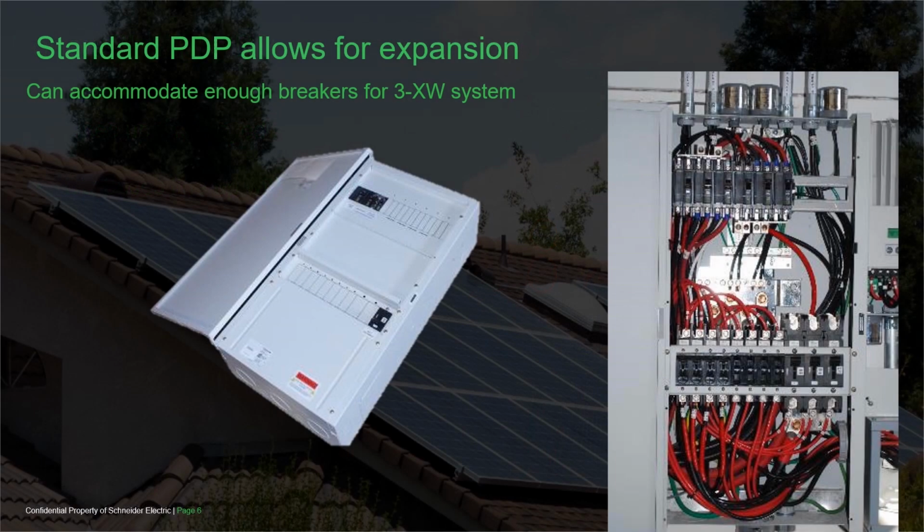The standard XW power distribution panel was originally offered with the legacy XW and XW Plus models and carried over to the XW Pro platform. The standard PDP provides enough AC breaker positions to accommodate a triple XW Pro multi-unit configuration and also provides positions for 8 panel mount DC breakers for the charge controllers. Note there is plenty of room for installers to get their hands in there.